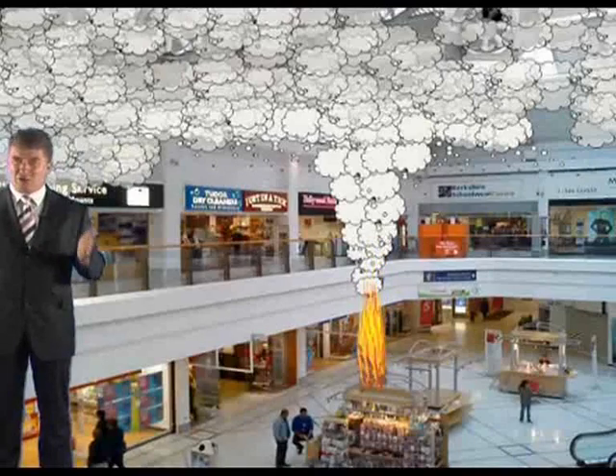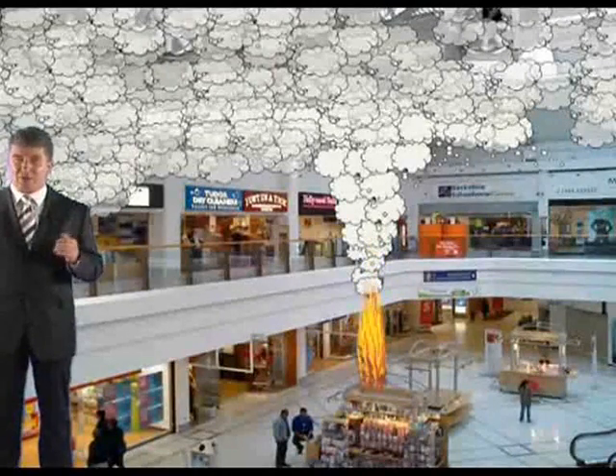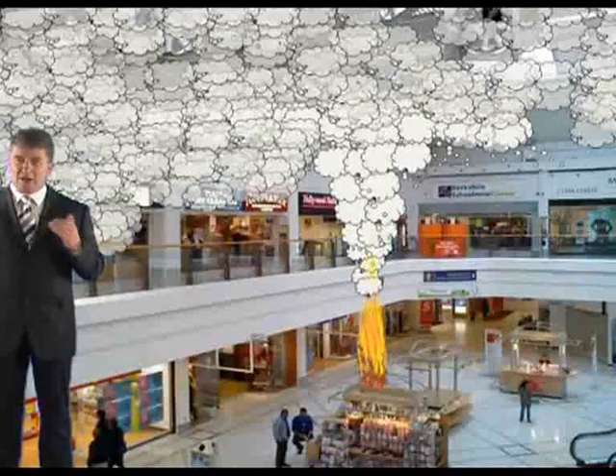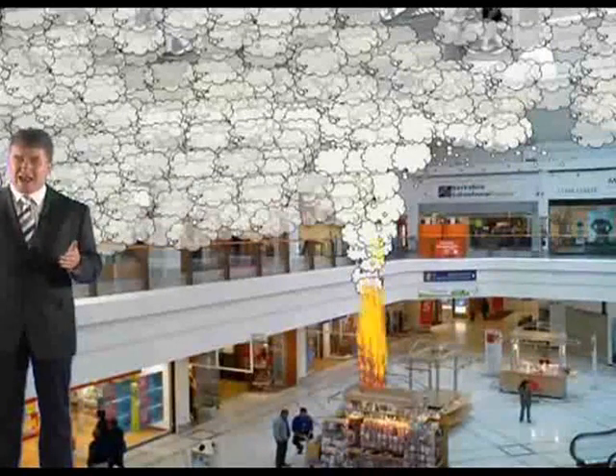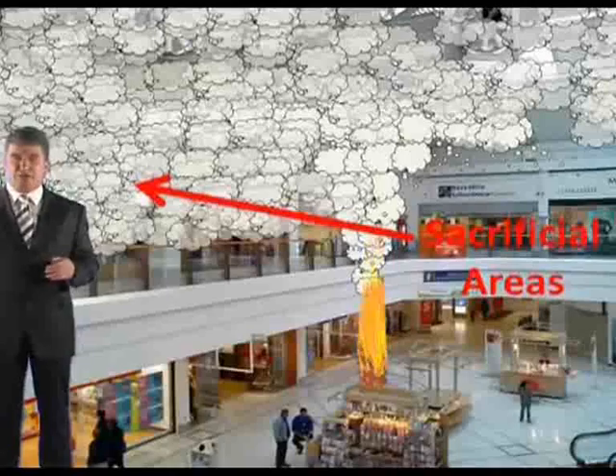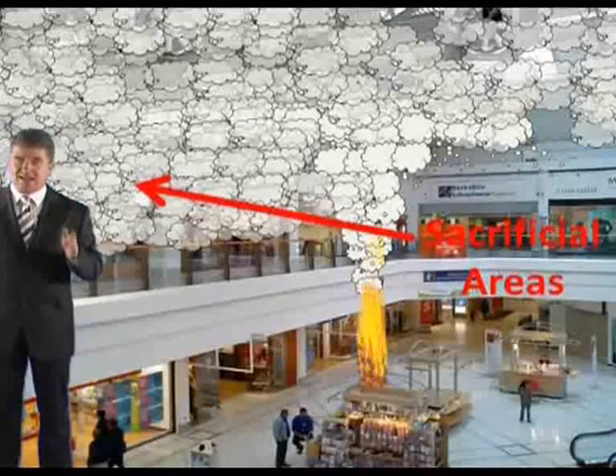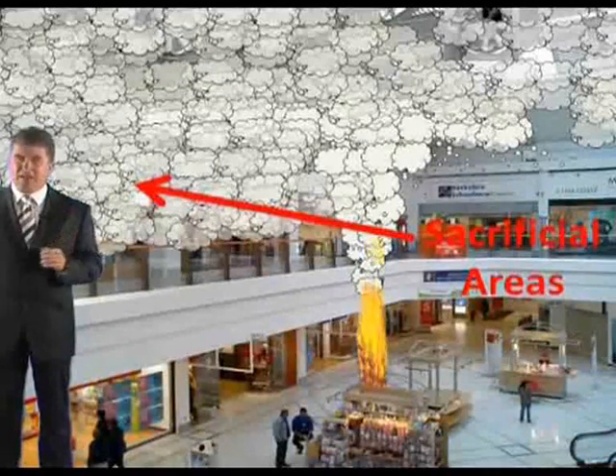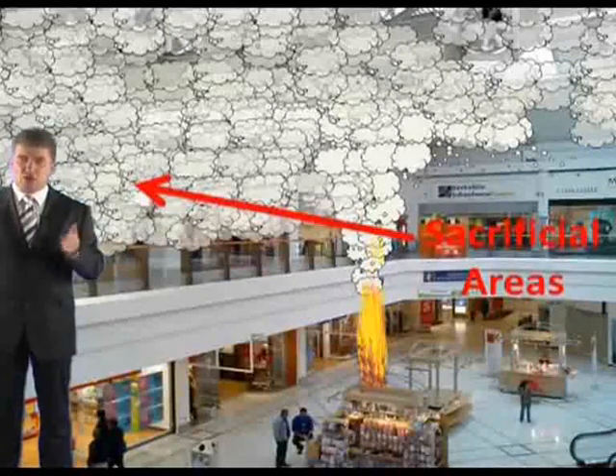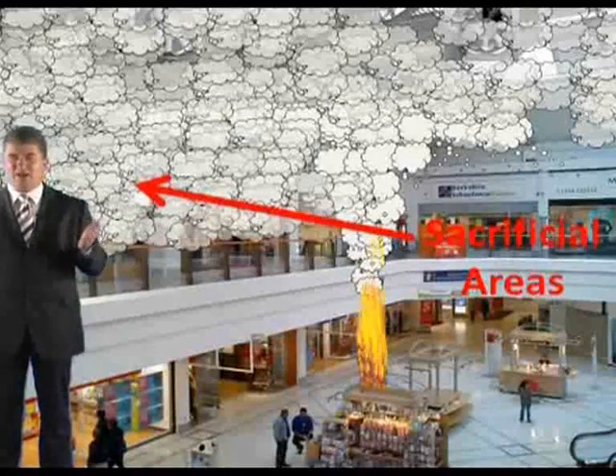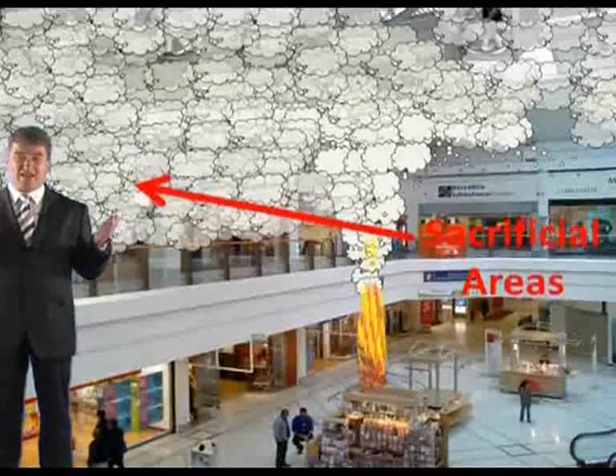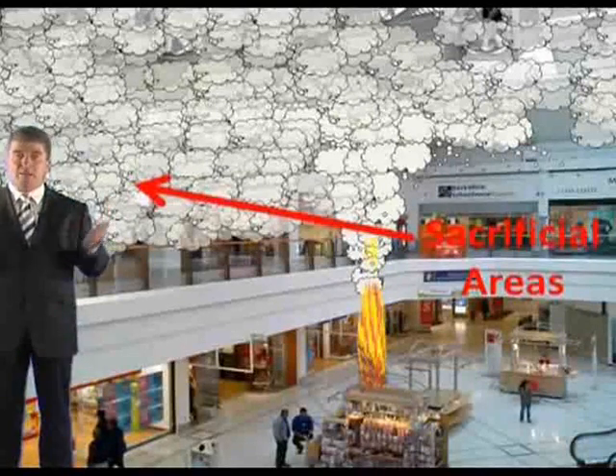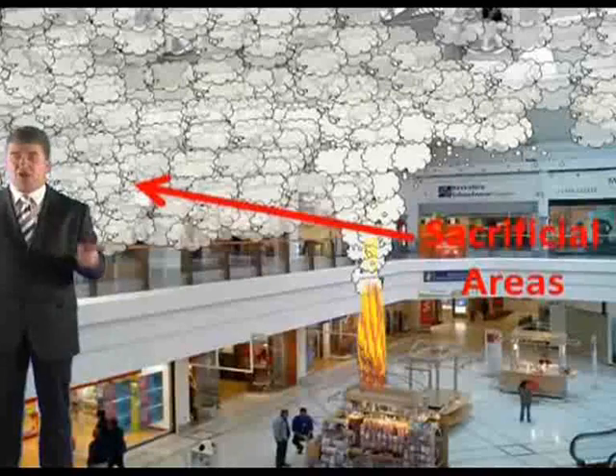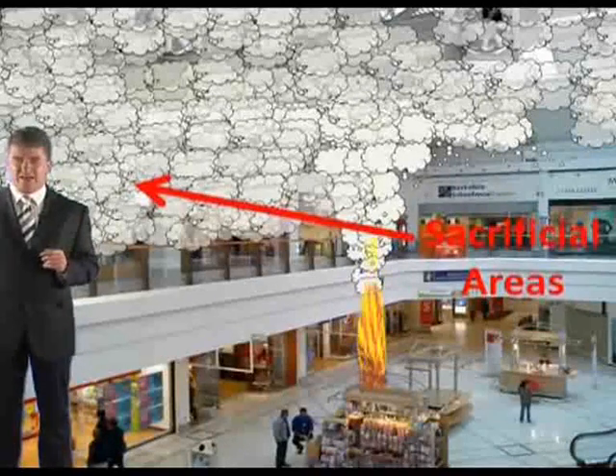Now, we've also got to look at sacrificial areas when designing these systems, because it should be noted that there are times when smoke would be allowed to enter rooms or areas that are prone to smoke damage, and those times are when the designer, in consultation with the building user, has decided that the areas under threat can be considered to be sacrificed in the unlikely event of a fire occurring. In other words, we're not worried if the smoke gets in these areas, there's no occupants in there, or they'll be gone because they meet the acceptable travel distances, they'll be gone by then. These are called sacrificial areas.